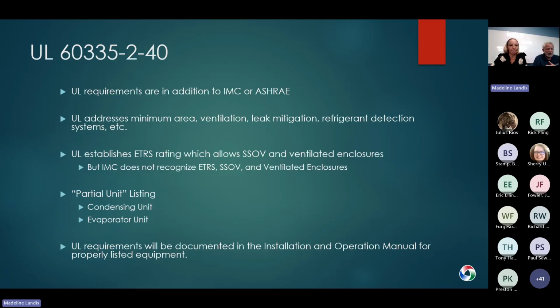In order to follow the UL instructions, you still will need to provide for refrigerant detection and certain volume or space area requirements above and beyond what's in UL, and above and beyond ASHRAE. You may have avoided a refrigeration machinery room, but you still need a certain amount of area to install this equipment in. There are specific listings for partial units. We certainly know about condensing units. Any condensing unit you buy commercially will be listed to this standard now. But it's the evaporator side that is a little bit more confusing. And I'm just going to leave it at that for now.